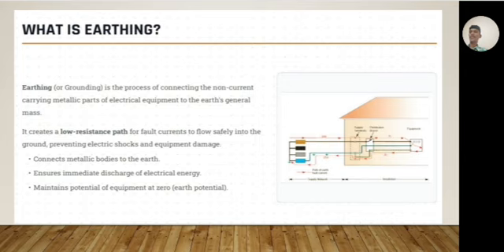Second point, it creates a low resistance path for fault currents to flow safely into the ground, preventing electric shocks and equipment damage. First point, connect metallic bodies to the earth. Second point, ensures immediate discharge of electrical energy. Third point, maintains potential of equipment at zero. This is the diagram of the earthing.